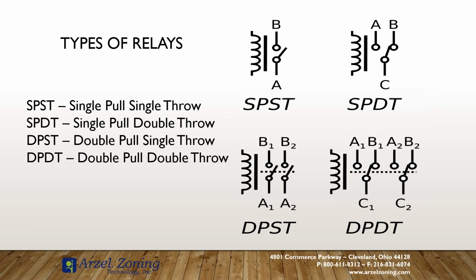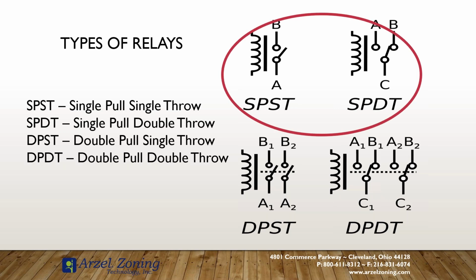We got a lot of different types of relays in the industry, but the ones that we're most familiar with in the residential light commercial are the SPST and the SPDT, single pole, single throw, or single pole, double throw. And more commonly, that relay on your truck is probably going to be a SPDT. So that coil controls a single set of contacts. Now you might have the DPDT. That's not quite as common. Usually we're going to run into those more with the industrial controls.